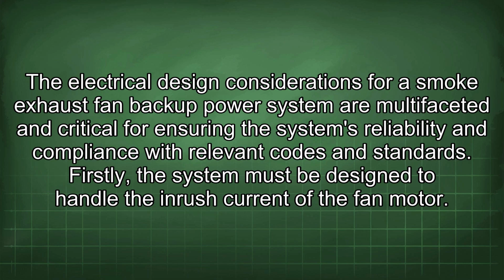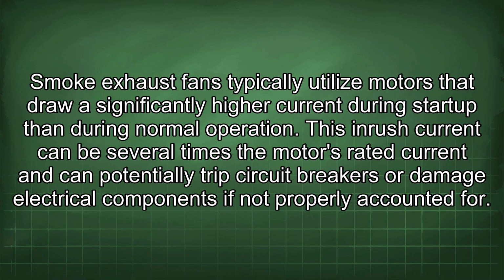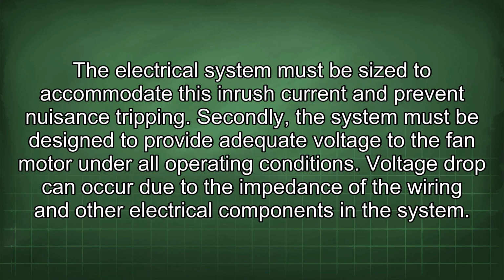Firstly, the system must be designed to handle the inrush current of the fan motor. Smoke exhaust fans typically utilize motors that draw a significantly higher current during startup than during normal operation. This inrush current can be several times the motor's rated current and can potentially trip circuit breakers or damage electrical components if not properly accounted for. The electrical system must be sized to accommodate this inrush current and prevent nuisance tripping.